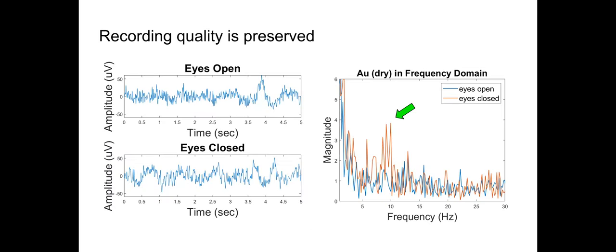So another thing that we also wanted to validate is that you can still take an EEG recording in this type of setup. And obviously, while we didn't do this in a scan, because that causes a lot of other interfering factors that would need to be accounted for, when the electrode is simply in the coil on the person's head, we've shown that you can still take a good recording and get good contact with the skin. So this is a really simple test that you can do when you take an EEG.